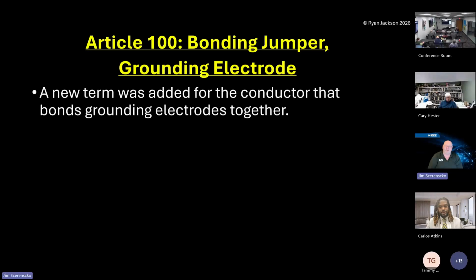If you don't understand the definitions, how in the world can you design it, install it, or enforce it if you don't know what it means? Okay? So to me, you have to understand the definitions first before you can ever do anything else. If you don't know what a receptacle is versus an outlet, that's a problem, because the code says that all outlets in these rooms shall be arc fault protected. An outlet is any point on the wiring system where electricity is used for utilization equipment, and then there's a definition for what utilization equipment is. Okay? So you have to understand the definition.